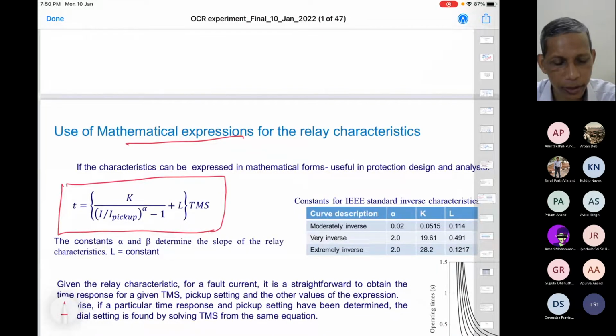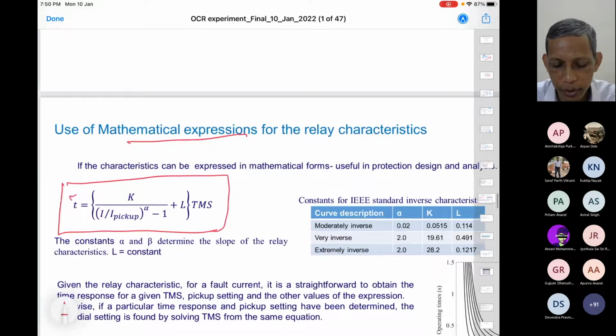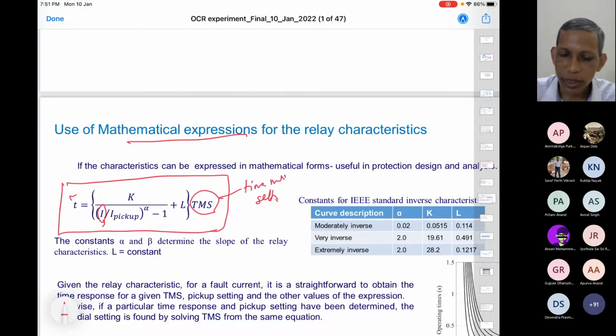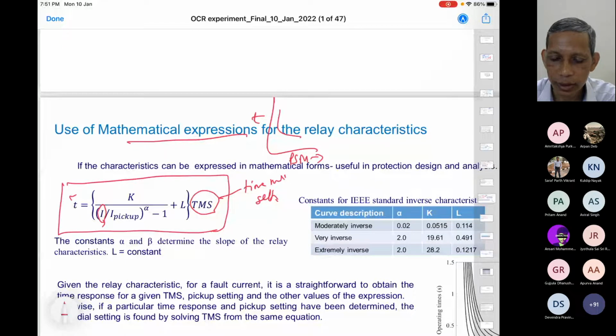Now, what is the decision time T? The decision time T is in terms of K upon (I over I pickup) to the power alpha, minus 1, plus L, a constant, times the TMS, time multiplier setting. This I is the relay current, that is the system fault current level, divided by the I pickup setting. Time multiplier setting, earlier we were discussing. Okay? So any characteristic curve which we saw, time versus the corresponding PSM, is governed by this equation. Agree?